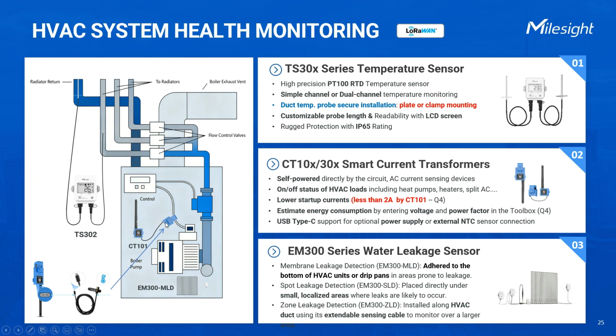You can see a typical use case in the image: the CT sensor clamped on the wire powering a boiler's circulating pump. It tells you whether the pump is running, reports current values as often as every second, and helps spot abnormal behavior early. An optional external temperature sensor can also be added to monitor for wire overheating.